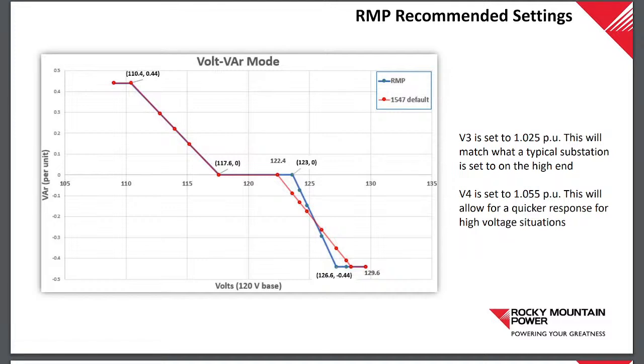And so a lot of times at our substations, the typical substation, we have it set the voltage at the sub at 122.5 to 123 volts. So at the subs, we're already at 123 volts. So we don't want to start regulating that voltage until we kind of get past what we're already at the substation. So we got a little change there. We're still well within the range that's allowed in the IEEE standard.